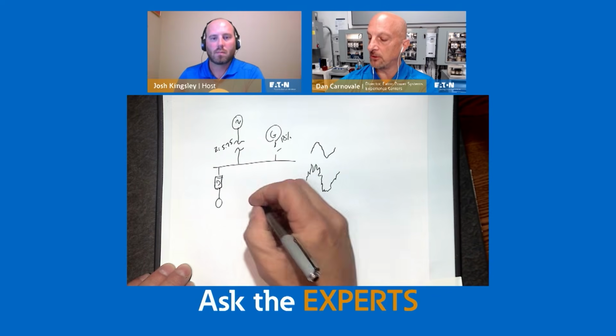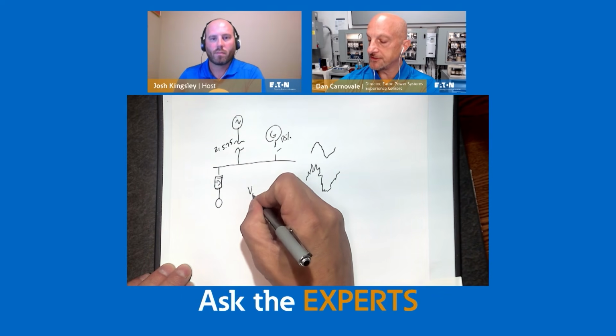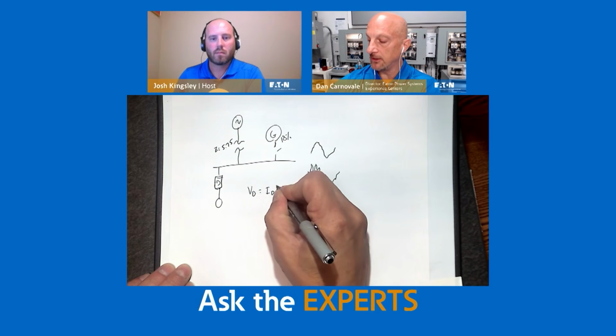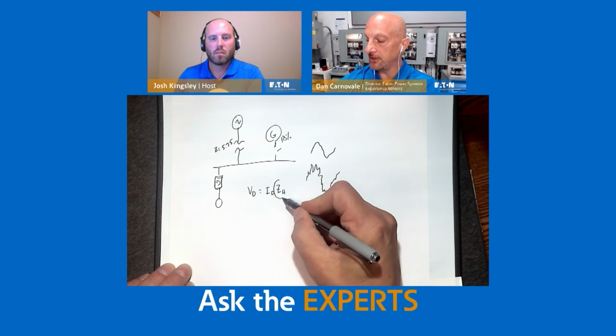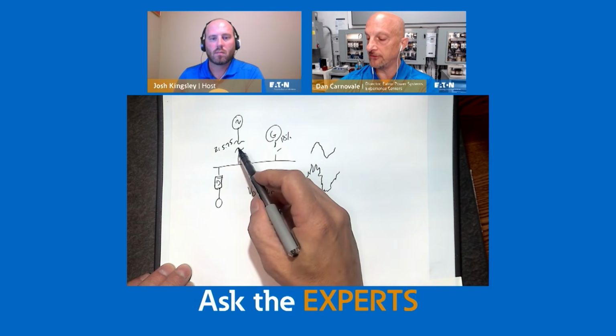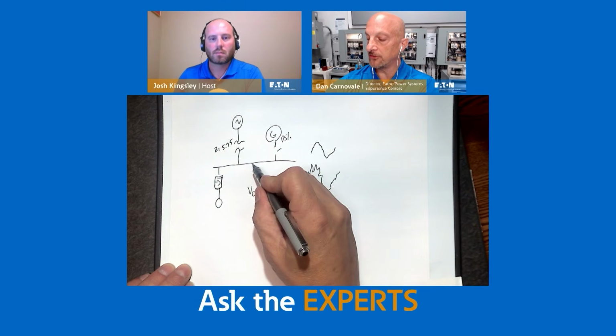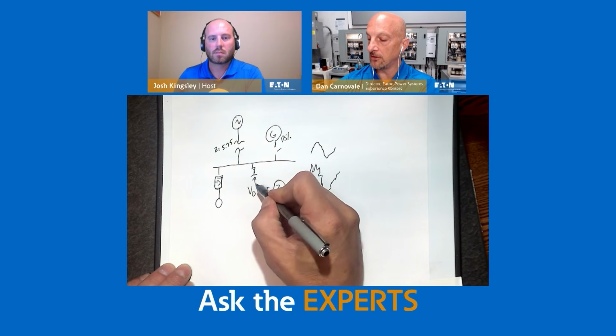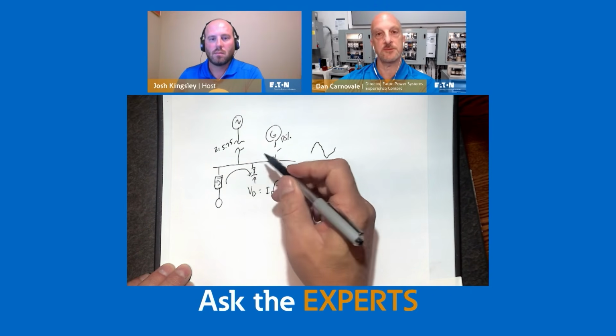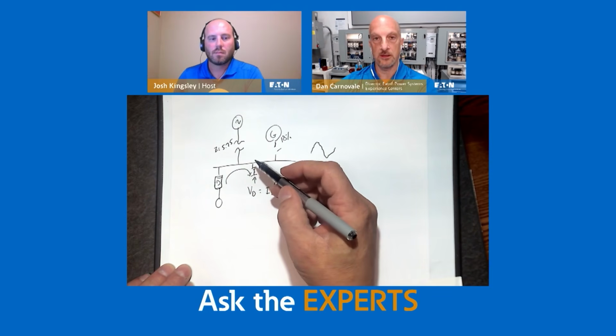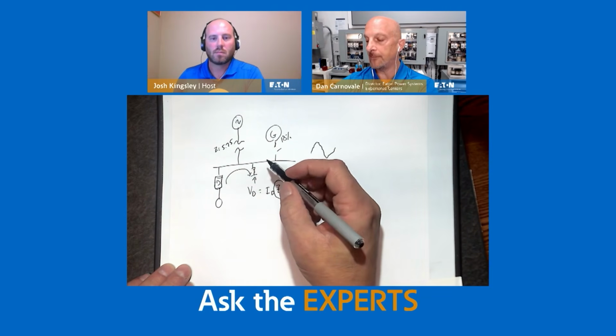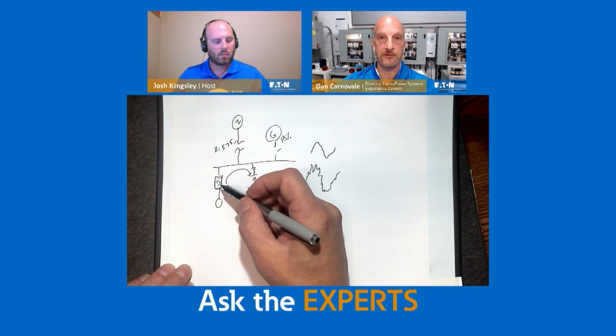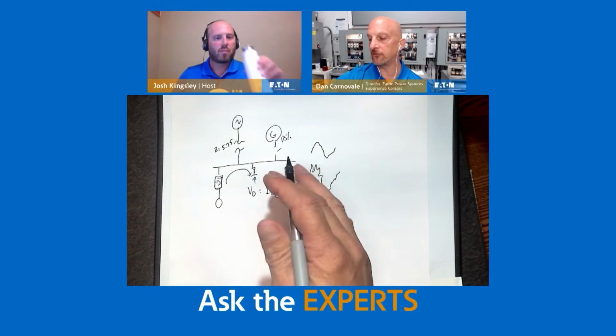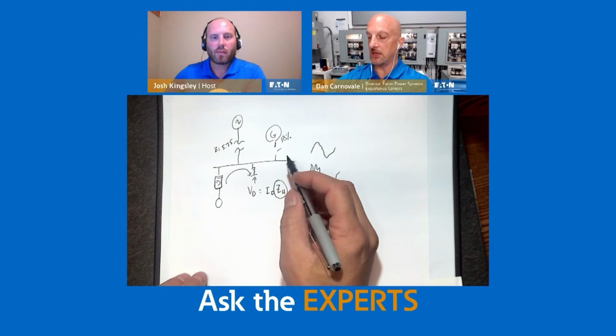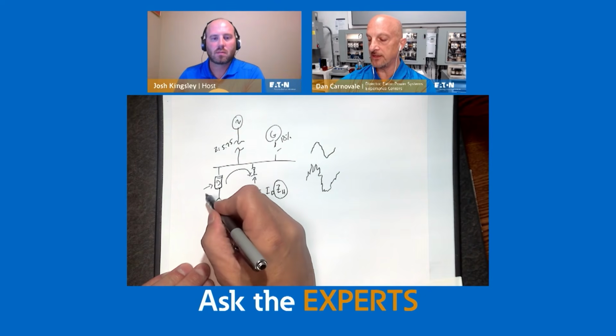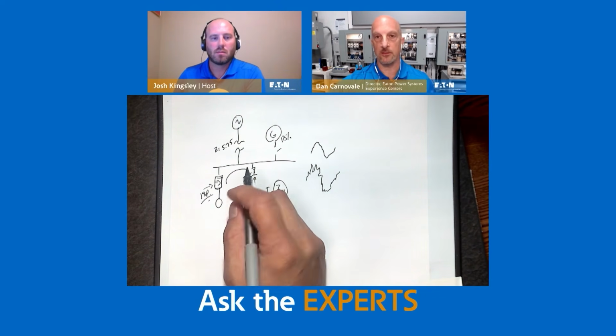And the reason is, remember, going back to Ohm's law, voltage distortion equals current distortion times harmonic impedance. And if the harmonic impedance here is 3 times on the generator what it is on the transformer, guess what? If I put a single solution in here, then all the harmonic current goes here no matter which source I'm on. So sometimes the answer is corrected on the system level. And again, this is drawn as one drive, but this could very well be 10 MCCs full of drives. The other thing is, let's say I didn't want to have to deal with this after the fact. If I make this 18 pulse, 90% of the time, I don't have to think about it anymore.